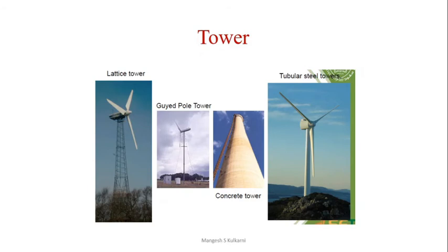Studies have shown that the added cost of increasing tower height is often justified by the added power generated from the stronger winds. Larger wind turbines are usually mounted on towers ranging from 40 to 70 meters tall. Towers for small wind systems are generally guyed design. This means that there are guy wires anchored to the ground on three or four sides of the tower to hold it erect. These towers cost less than freestanding towers but require more land area to anchor the wires.